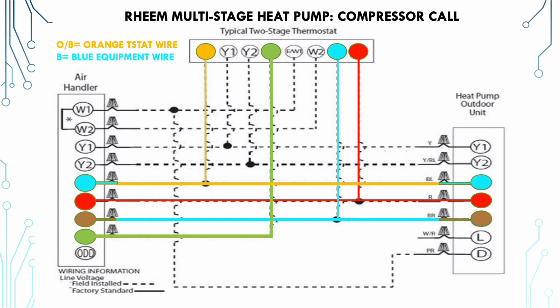Orange. So, like I said, Rheem likes to use the blue wire for the OB contact. And just to recap what this means, on most brands that are out there, the reversing valve of the heat pump sits naturally in a heating position. And when you get a 24-volt call on the OB contact from the thermostat, it's energizing that reversing valve to move into the cooling position, and that is called energizing on O. Rheem is naturally in a cooling position with the reversing valve. When you ask for heating, 24 volts is applied to the O wire, and that is going to energize the reversing valve into heating mode.